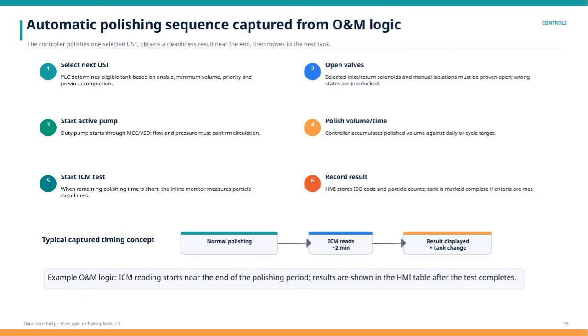Next, the system opens the necessary valves. This means the selected inlet and return solenoids, along with any manual isolations, must be confirmed open. Any incorrect valve states are interlocked to prevent errors. Once the valves are confirmed, the duty pump starts through the motor control center or variable speed drive. The system then verifies flow and pressure to ensure proper circulation. During polishing, the controller keeps track of the polished volume against a daily or cycle target. This way, it ensures that each tank receives the correct treatment volume or time.